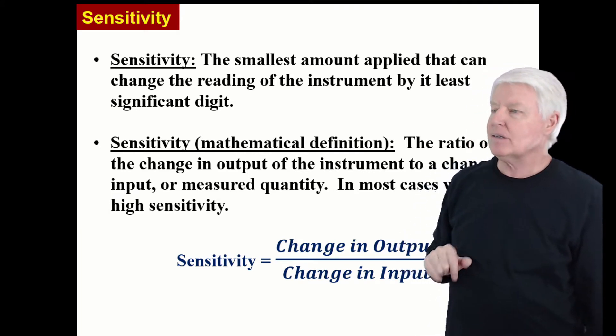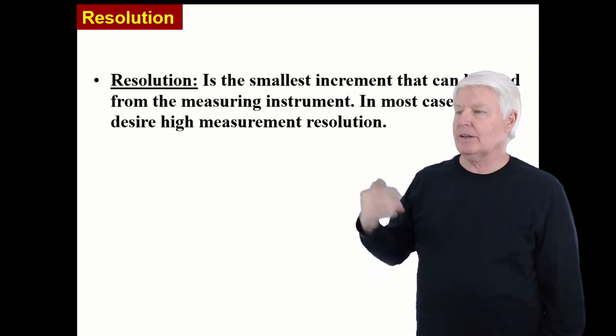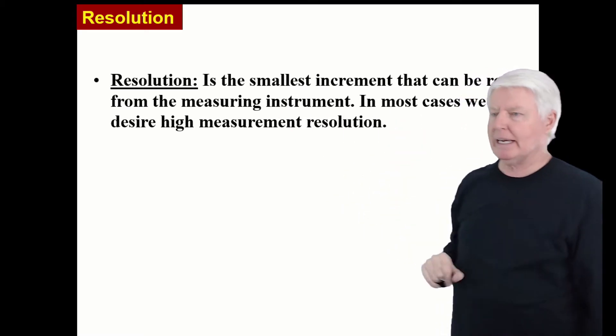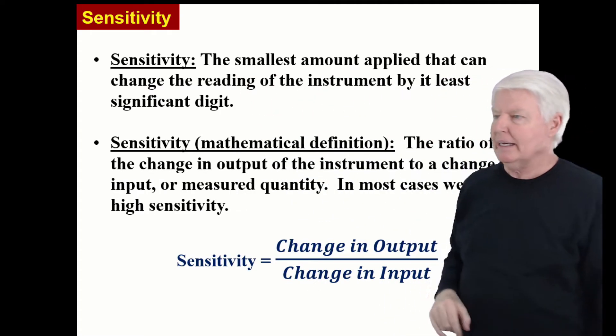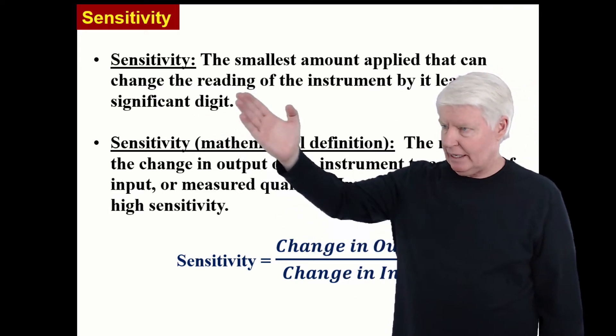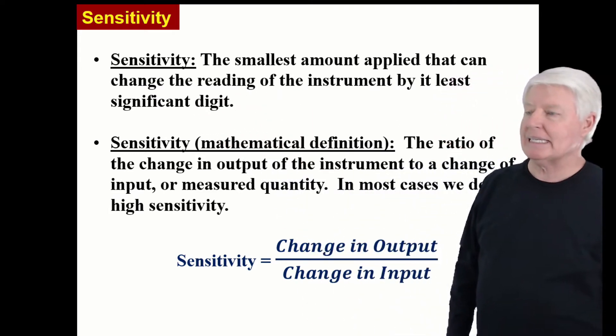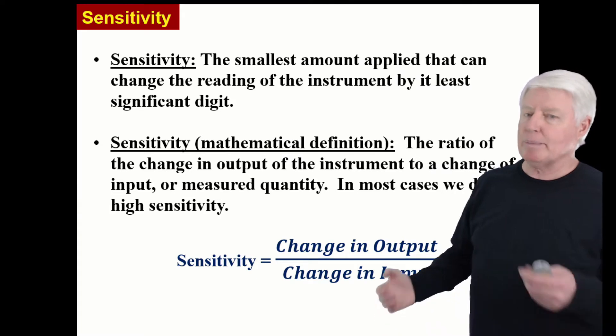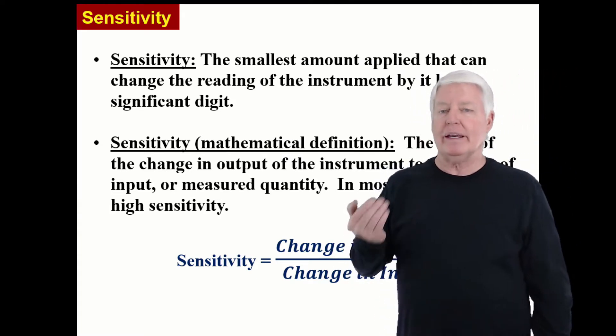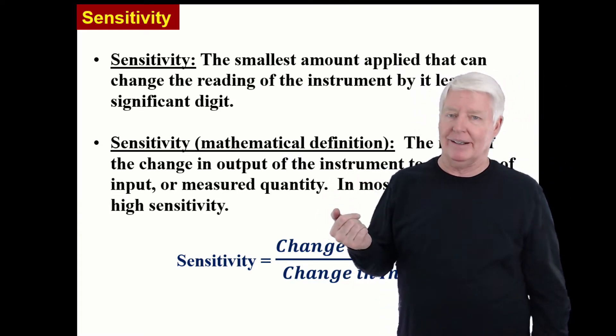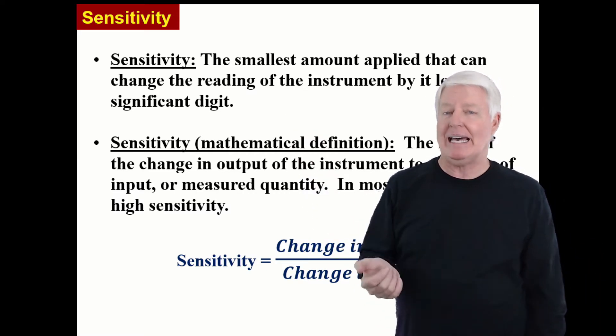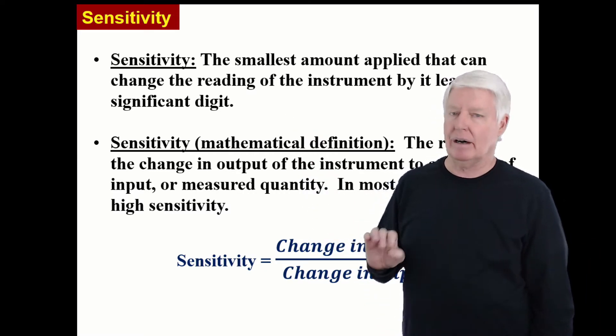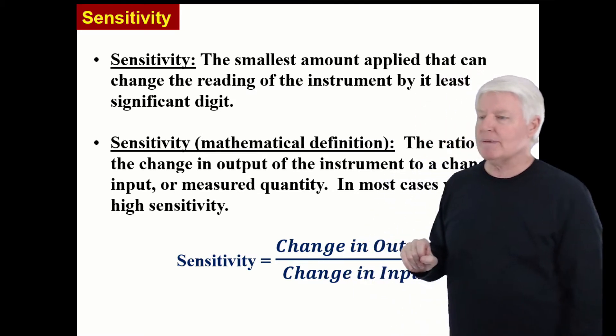Sensitivity is the smallest amount applied that can change the reading of the instrument by its least significant digit. So you can compare the two. Smallest increment that can be read from the measuring instrument versus the smallest amount applied that can change the reading of the instrument by its least significant digit. So they're pretty close and I know you're thinking, well they're the same thing because sensitivity is based on the resolution. In many cases that is the case, but not in all.